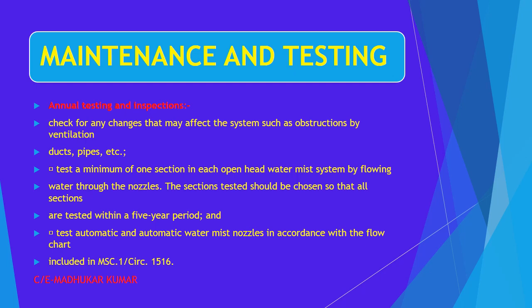Test a minimum of one section in each open head water mist system by flowing the water through the nozzles. At least one section must be operated. The section test should be chosen so that all sections are tested within the 5-year period. Okay, so when we are talking about actual water flow, we have to test in such a manner that all the sections are completed within a 5 year period.